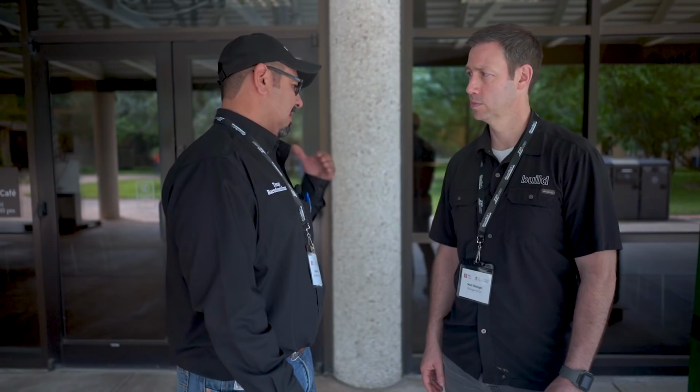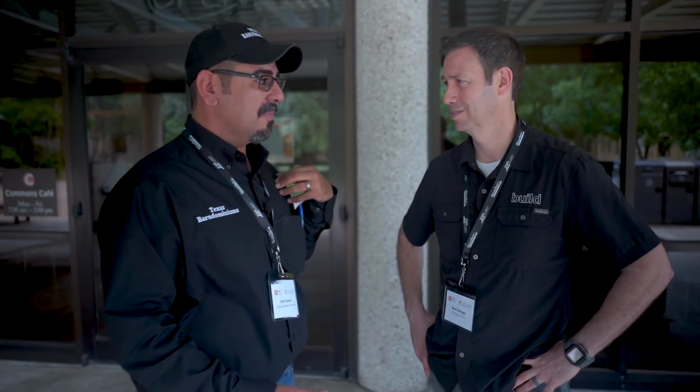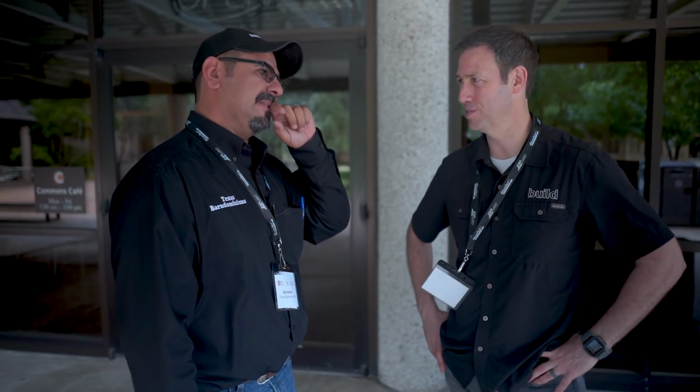That's good. As you know, big issue with foam insulation is putting in too big of a unit. Yeah, for sure. I had a guy call me 2 weeks ago, and he's trying to get me to help him because he bought a 1,200 square foot home with a 5-ton unit. Ooh, way too big. Yeah, I said, way too big, and he said, man, we're having. I said, let me guess, you're having moisture issues. He said, like you can't imagine. I said, no, I can imagine.